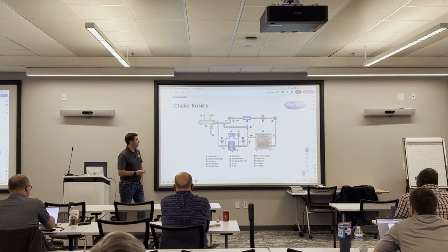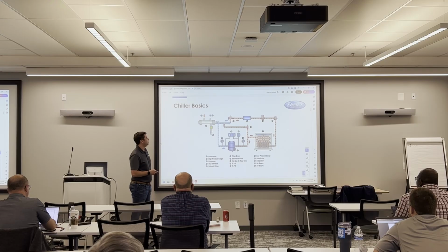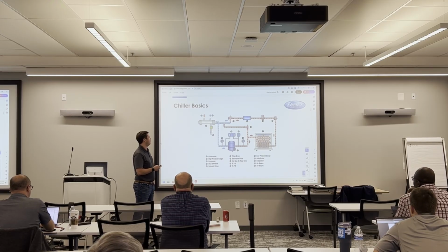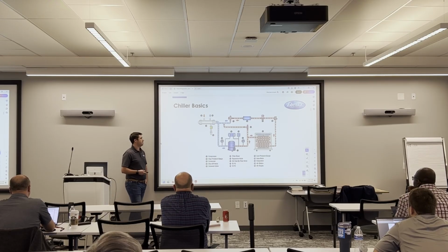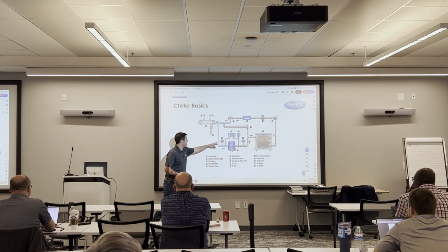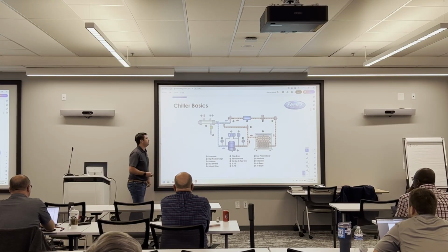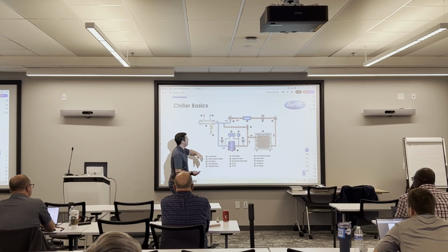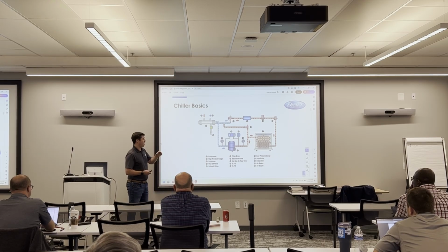So now we're leaving our condenser coil as a subcooled liquid. It's traveling through our liquid line, and it's going to go into our metering device. So this metering device is the smallest component on this whole system, but it's the most important because it's what's ensuring the gas leaving the evaporator is going to be a vapor. So if you're getting liquid out of your evaporator, the metering device is going to restrict itself and allow less refrigerant to flow through so you boil off that excess liquid.